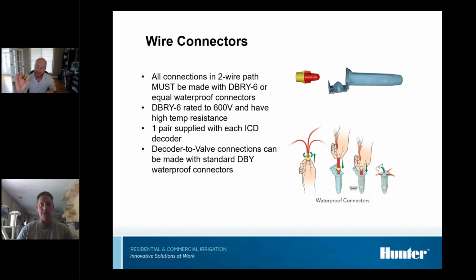I really encourage you to use that. I want to show this piece my buddy at Page Electric gave me. On one side is just a regular old wire nut, and over here is the wire nut we supply with the DBRY6. Do you see how much better grip and copper-to-copper connection you get with the one we supply? We're sending communication and information across that wire, so we want the highest integrity splice we can get, and these splice kits provide it. Always specify DBRY6 on your 2-wire path.